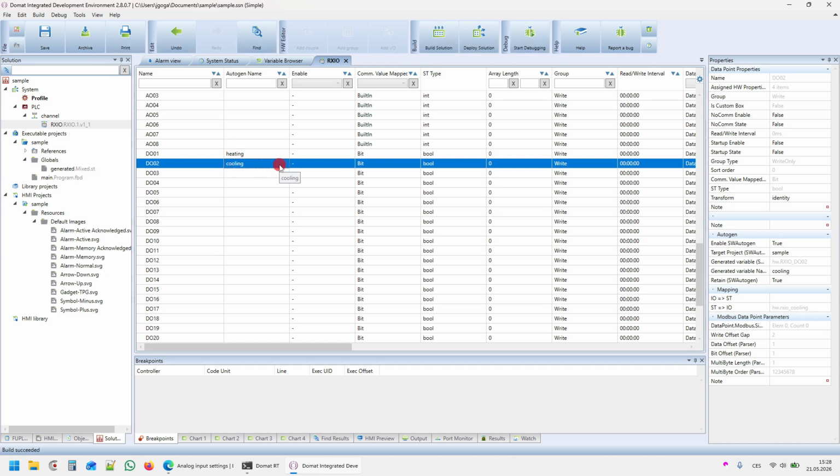Some PLCs of the Mark series have switchable analog inputs. They can measure resistance, voltage, and current. To measure current, in addition to changing the program, you need to turn on the dip switch for the given input. When using a temperature sensor based on PT1000, be careful about correct settings.